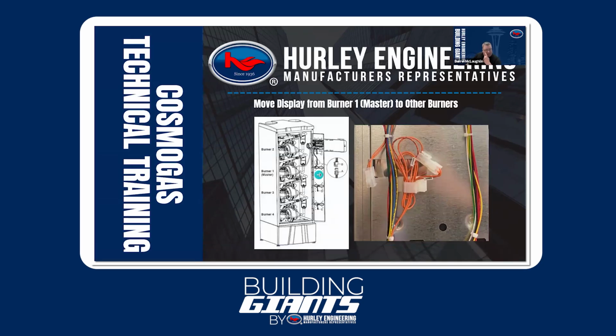Okay, another feature they've got. Commonly people run into this: let's say for whatever reason you've lost a master control, because it's a master-slave relationship for all of your controllers on this, right? One is going to act as the master to control the other three as slaves. Well, what if you're doing maintenance or you're pulling this one out or the master has been fried? Well, you've got quick Molex-style connectors that you can unplug and replug, and now you can move that master control and you've got a new master operational.